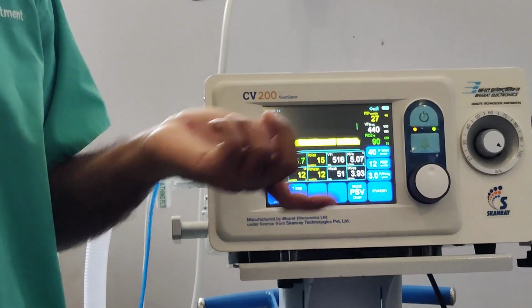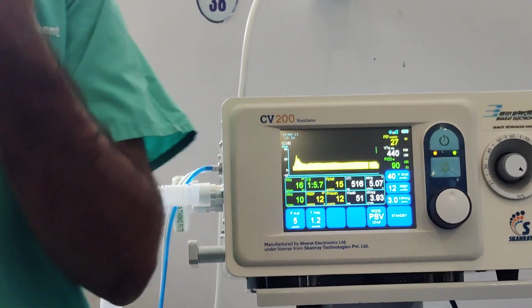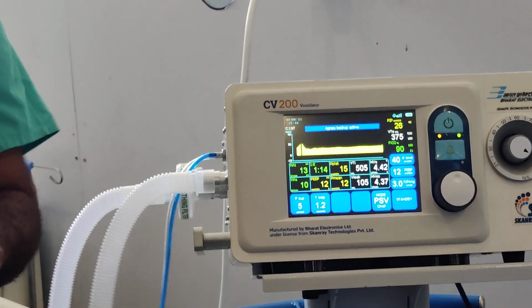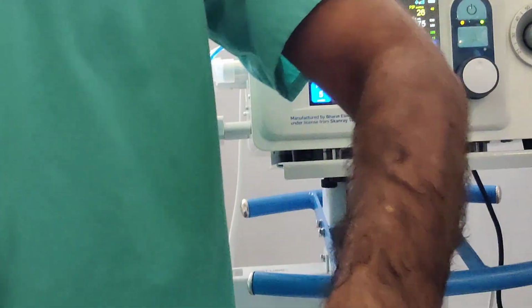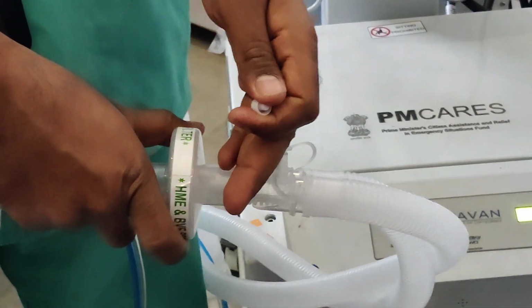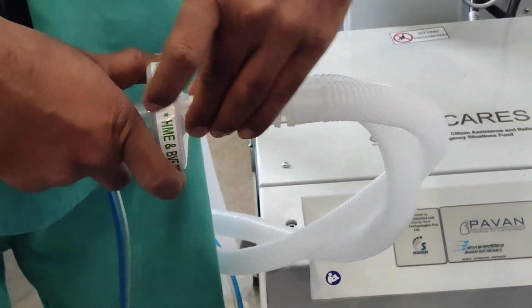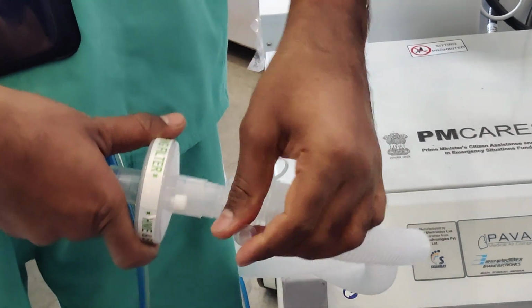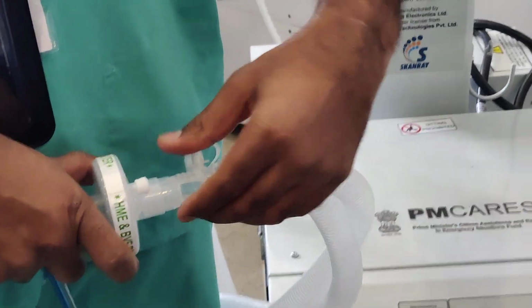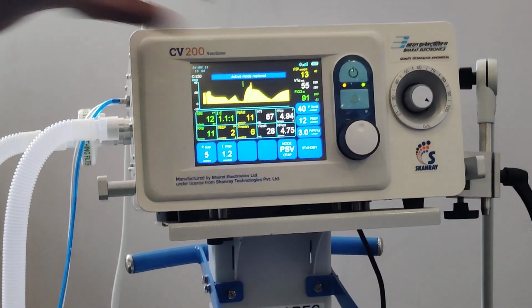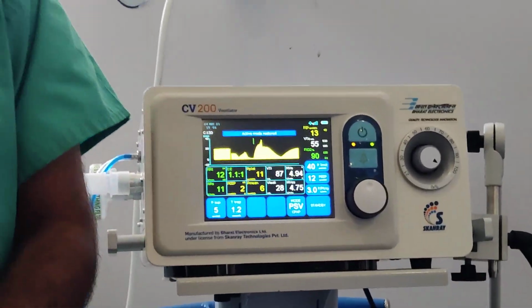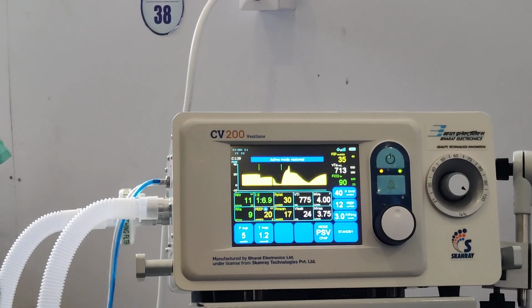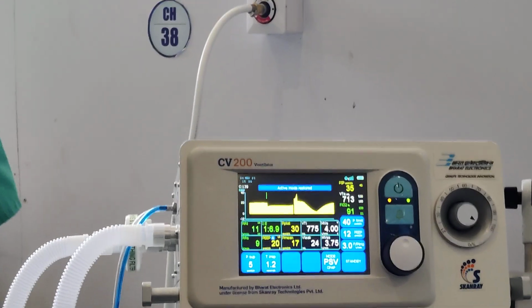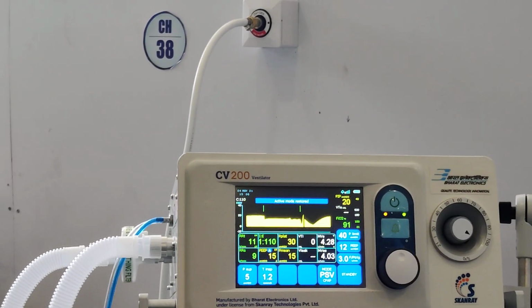The same thing can happen if your mask is not fitted properly. If any of your connections is loose, or if this connector comes out, volume will leak from here. If this connection comes out, volume can leak from here. So see this volume, and if there is any leak, make sure everything is fitted properly and the face mask is also fitted properly on the patient's face.